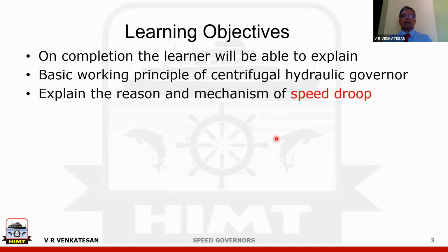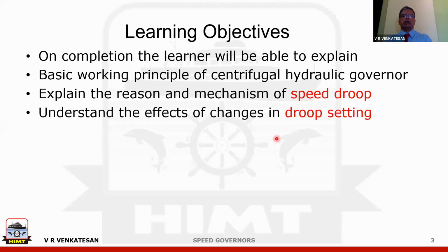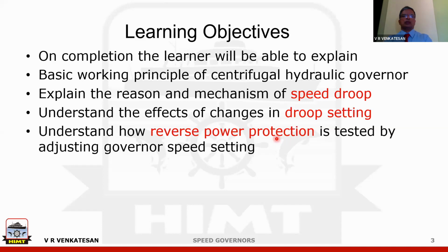Explain the reason and mechanism. Understand the effects of changes in droop setting. If droop settings are changed, what will be the effect, we can see. And understand how reverse power protection is tested. This reverse power protection is something which is frequently tested on board the ship, and how the testing takes place can be understood in the context of the droop graph.